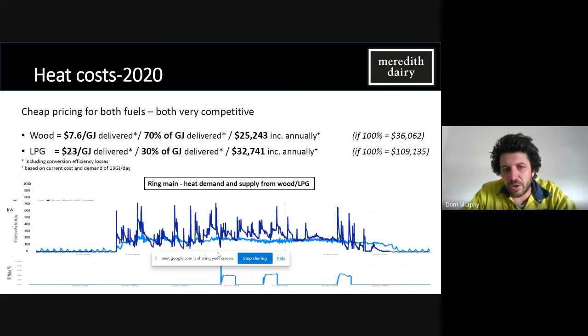But that 70% of heat that came from wood chips was actually costing us less than the remaining 30% that we got from LPG. So over on the right, I've said if 100%. At that time, the determination was made that if we could figure out a way to get all of our heat from wood chips, it would cost us $36,000 a year. And if we decided to turn the wood-fired boiler off and rely purely on LPG, it would cost us nearly $110,000 a year. So a significant saving there, and there was a real focus to shift towards wood chips and figure out ways where we could get our boiler to run as efficiently as possible and run for as long as possible.